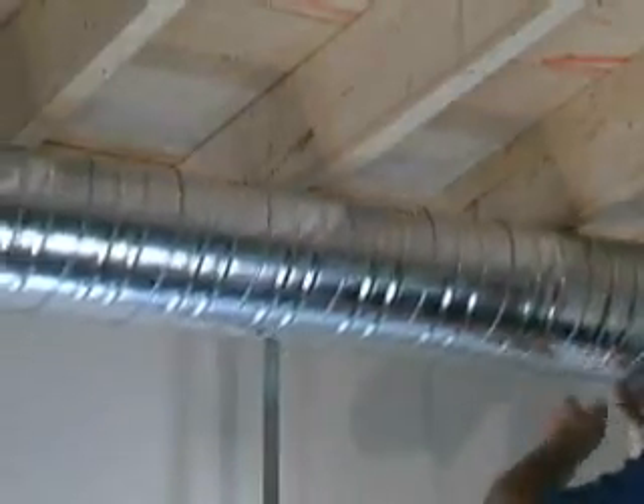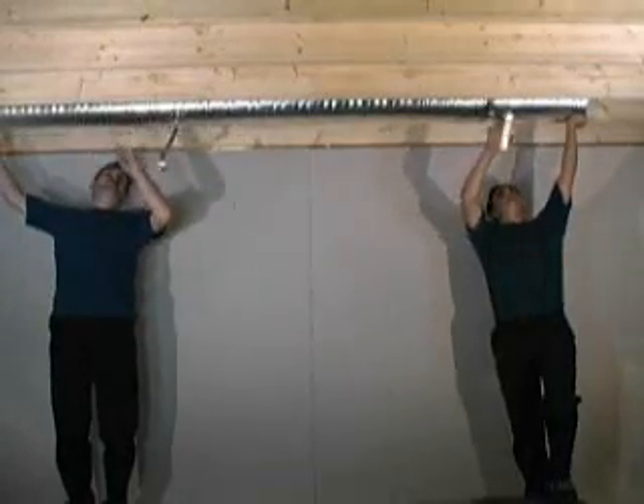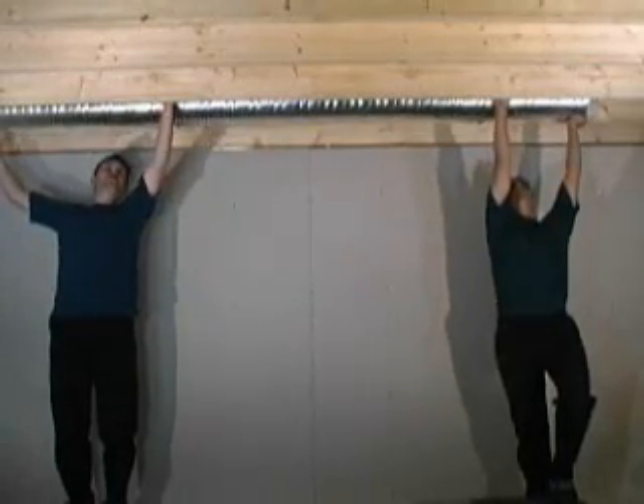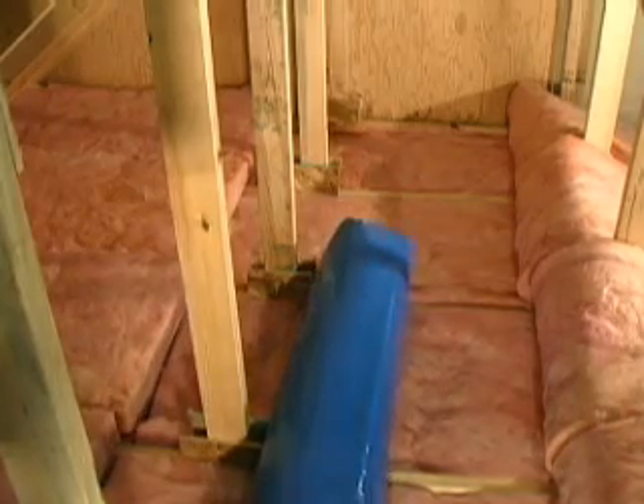In a suspended system, hang the plenum under the floor joists using sheet metal strapping. The plenum can also be concealed in the joist space depending on how the floor is constructed. In an attic, lay duct over the bottom chord of the roof trusses.